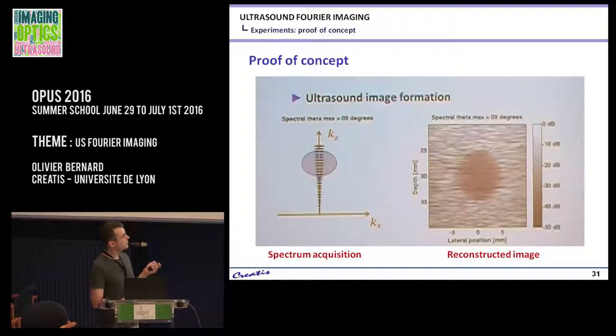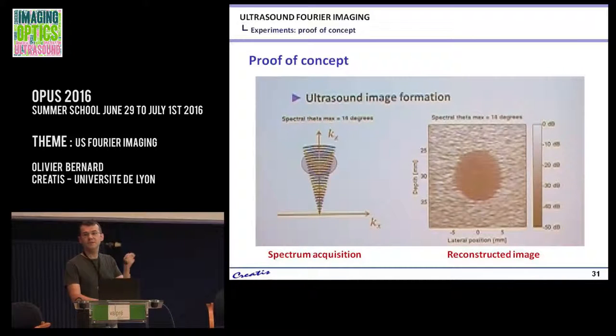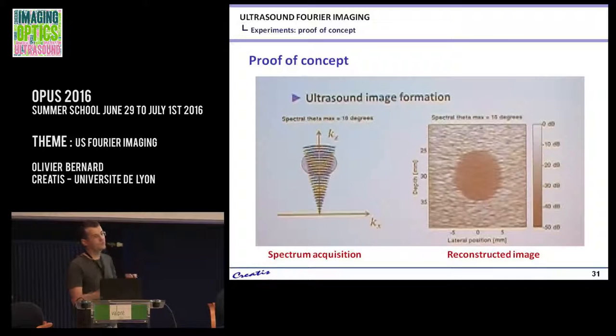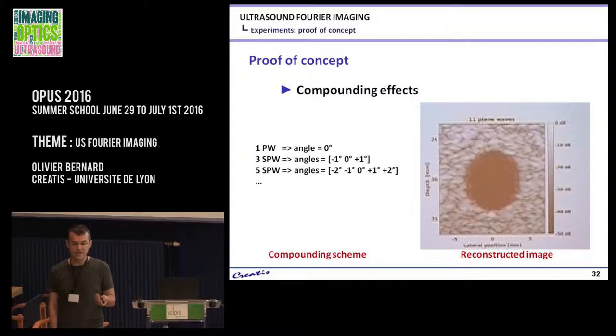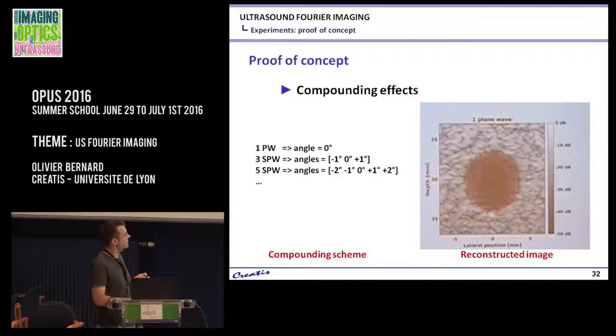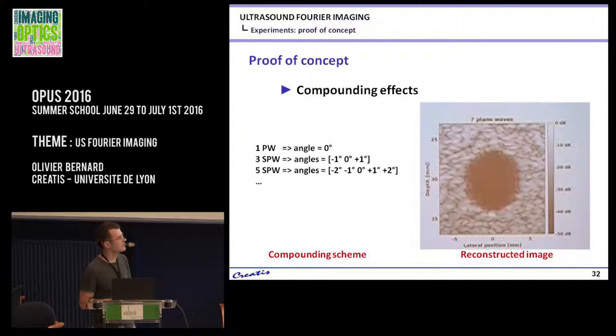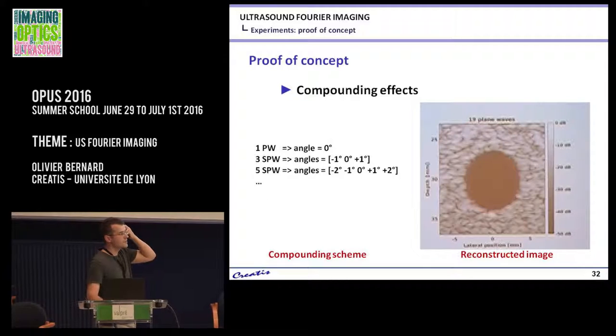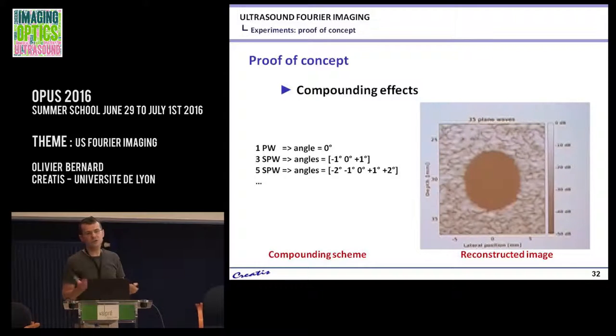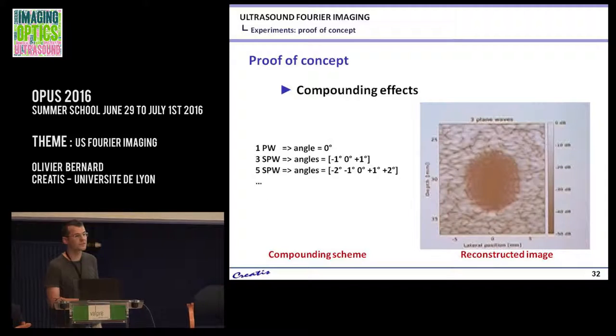We can also do compounding — instead of using a single plane wave perpendicular to the probe, you can emit several steered plane waves and apply the summation. This illustrates the interest of using steered plane waves. Each image I reconstruct uses a different number of plane waves in emission, while in reception I use the full densified spectrum. You can see the evolution and the trade-off: do you want the best image quality, or very fast acquisition?